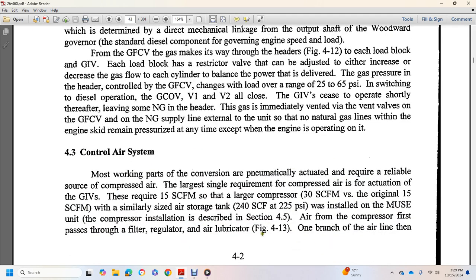Alright, 4.3, the control air system. Most working parts of the conversion are pneumatically actuated and require a reliable flow of compressed air. The largest single requirement of compressed air is the actuation of the gas inlet valves, which requires 15 SCFM. A larger compressor of 30 SCFM is used versus the original 15 CFM.